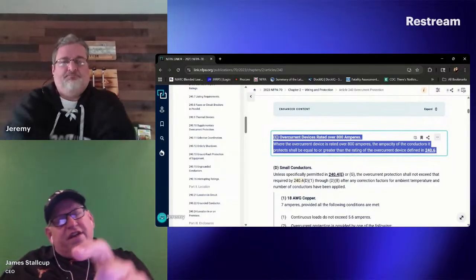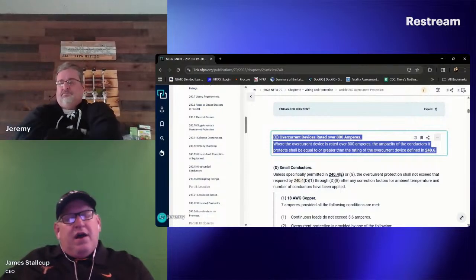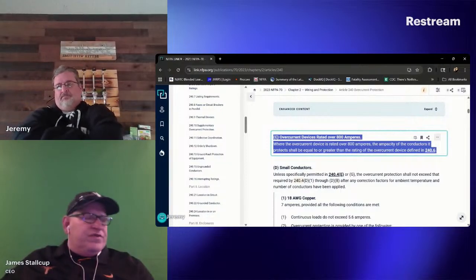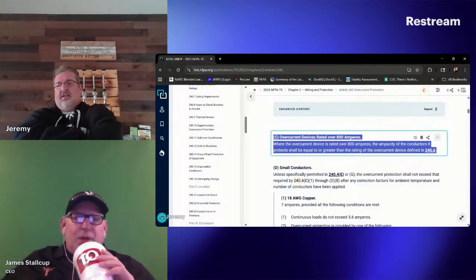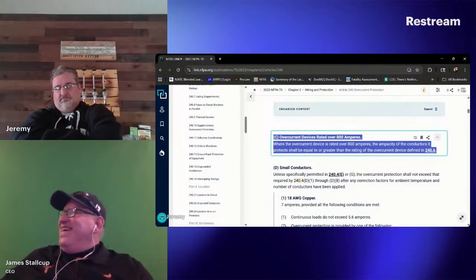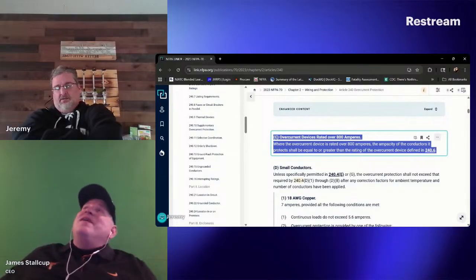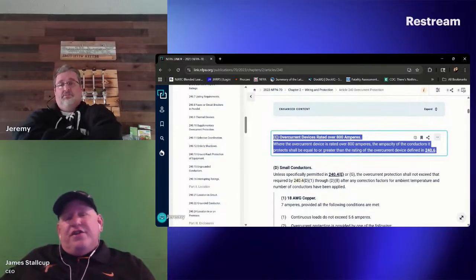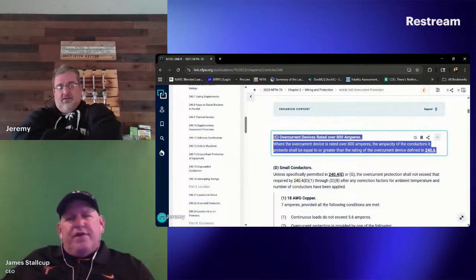Then you come over here and it tells you to go to Article 240, Part 1, and this is where your rules are. Where does it say anything about calculating anything in 240.4(C)? Oh my God. I just told you, you can go look at 210.19(A)(1), 210.3, 215.2(A)(1), 215.3, and 230.42(A)(1). Same rules for sizing the conductors and overcurrent device.